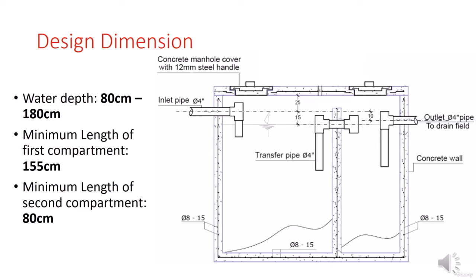Now let's check what are the design dimensions and requirements of the sedimentation tanks. The inlet pipe, the transfer pipe, and the outlet pipe must have a diameter of 4 inches. The inlet pipe must be placed 25 centimeters below the slab. The transfer pipe is placed 15 centimeters below the inlet pipe, and the outlet pipe is placed 10 centimeters below the inlet pipe.